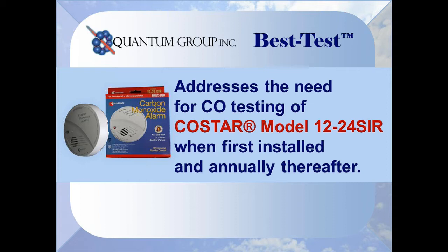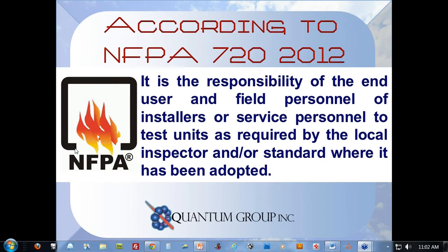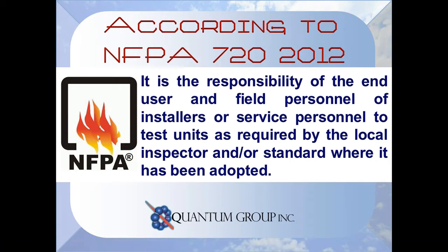You would be testing our Model 1224, the COSTAR Model 1224, and the alarm or carbon monoxide detector that are used in systems must be, according to NFPA 720, tested at the time of installation and annually thereafter.